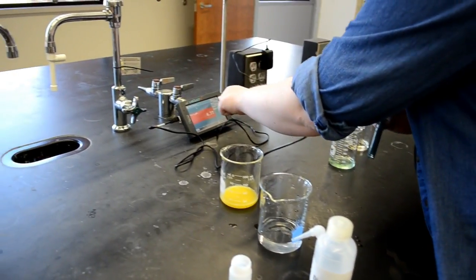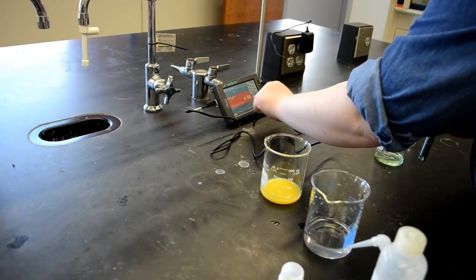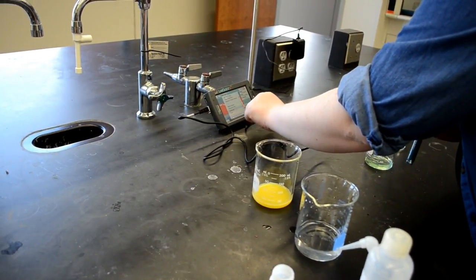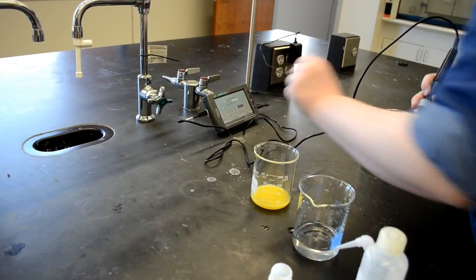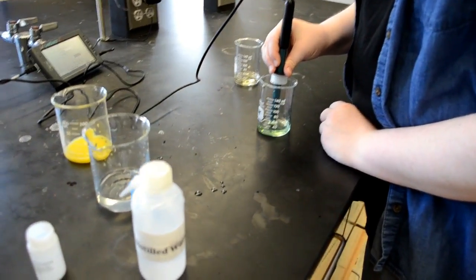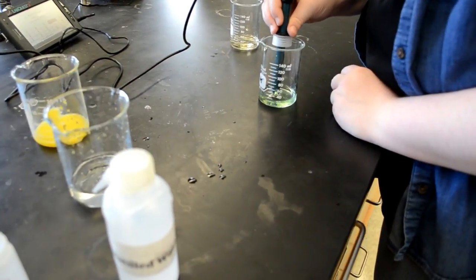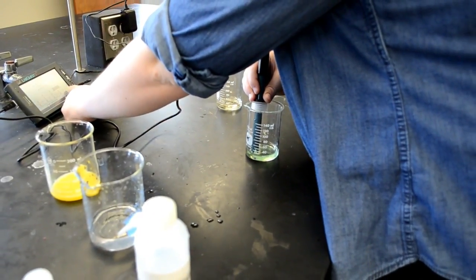To calibrate your pH meter, select Sensors at the top of the pH meter screen. A list should appear. When it does, choose Calibrate Now and place the probe in your first solution with the known pH. Submerge the end of the probe completely in solution and stir gently. Be careful not to hit the beaker with the probe. Input the pH of your first known solution and click OK.